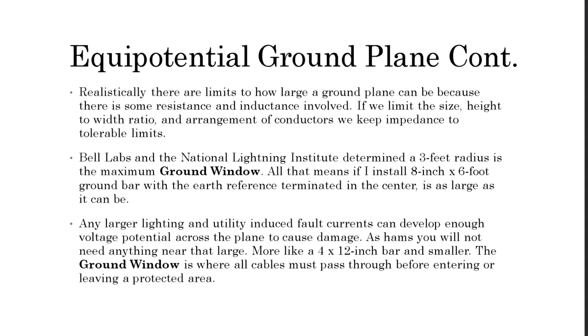Realistically, there are limits to how large a ground plane can be because there is some resistance and inductance involved. If we limit the size, height to width ratio, and the arrangements of the conductors as they fall in the ground bar, we can keep the impedance to low tolerable limits. Now, studies from Bell Labs, National Lightning Institute, and some other listing agencies determined a 3-foot radius is the maximum size you can make a ground window.